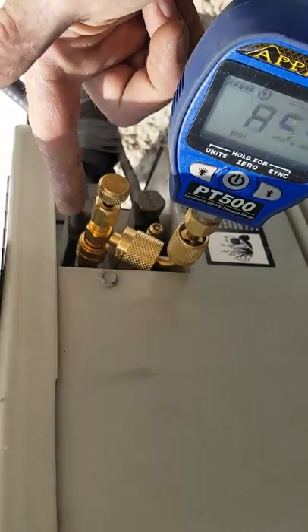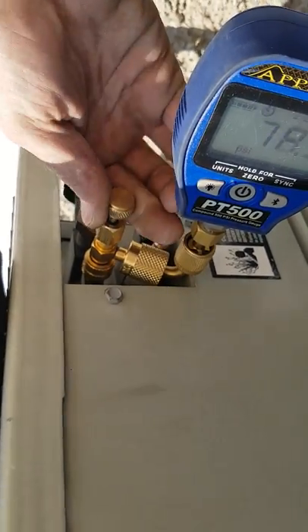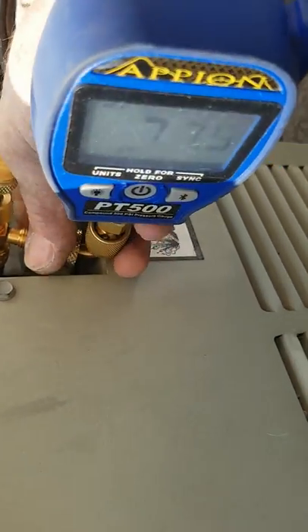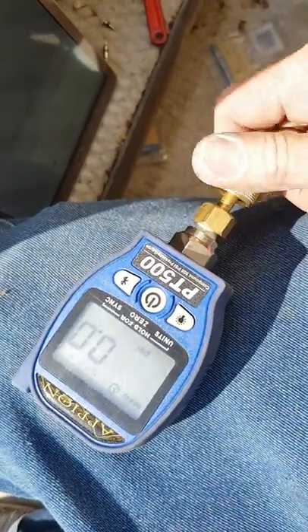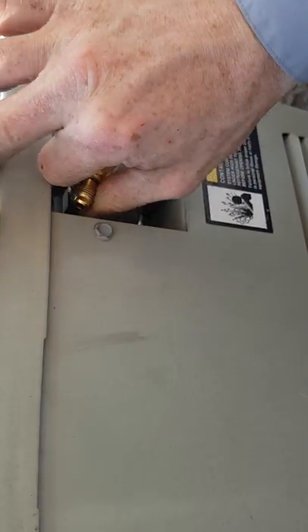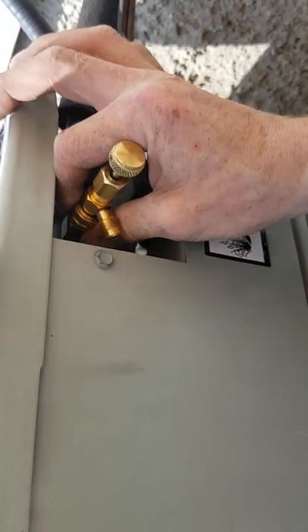I've checked my pressure and I'm ready to disconnect, but first I'm going to backseat the core depression tool once again — loosen this off to release pressure off the gauge. There's just a tiny little bit when you disconnect — and there's my gauge. No refrigerant release, no refrigerant release. Now I can take my core depression tool off. Thank you very much, Trane, for the amazing amount of clearance on this unit.